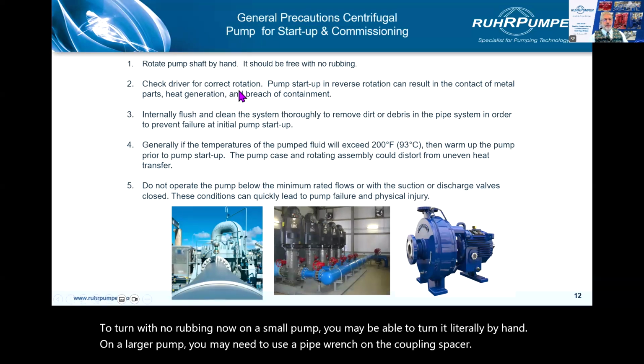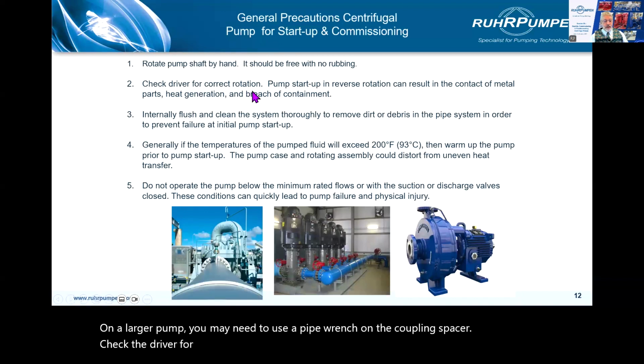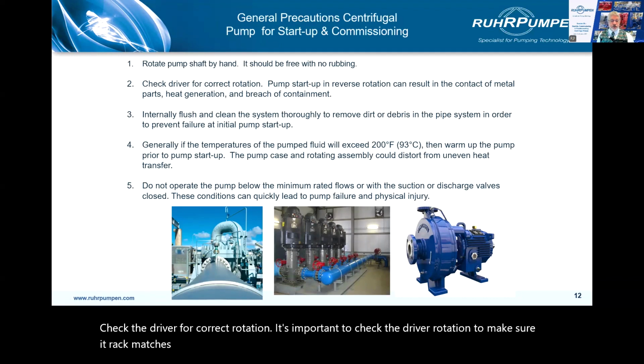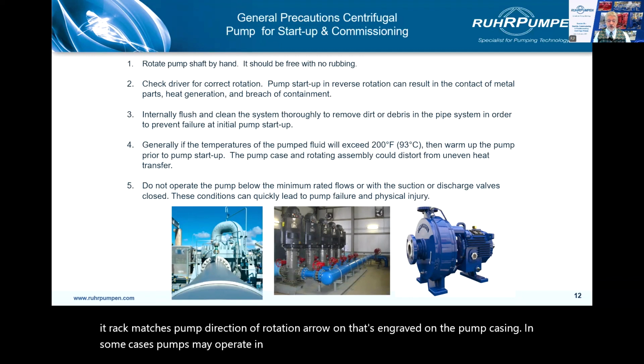Check the driver for correct rotation. It's important to check the driver rotation to make sure it matches the pump direction of rotation arrow that's engraved on the pump casing. In some cases, pumps may operate in reverse, and that could be running at about a third of the design performance. Now, it may sound obvious, but it clearly isn't.